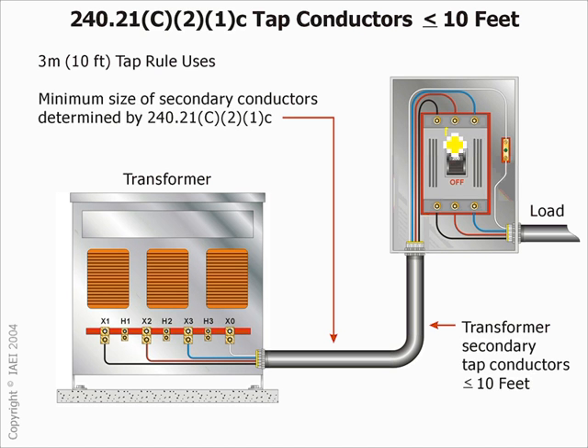Let's take one of them here. I'm going to make this one, guys, a 400 amp. My conductor, I know for a fact, has to be more than that, so I guess it's going to be 600. Okay, 600 amp. So the primary for this conductor, and I'm going to go to the max. Let's make primary 600 and secondary 240. Now we complicate things even more. Talk about engineers, huh? 240 divided by 600, right?